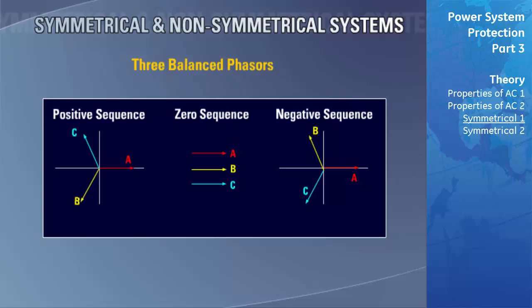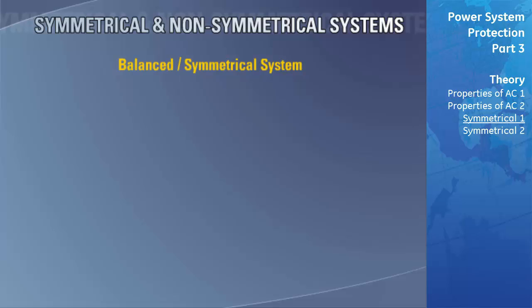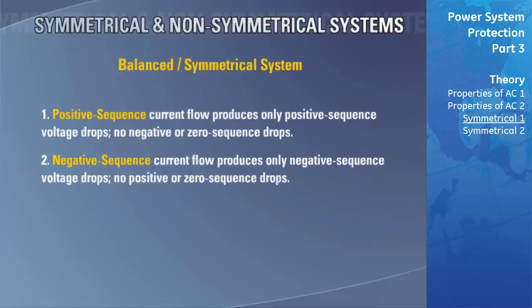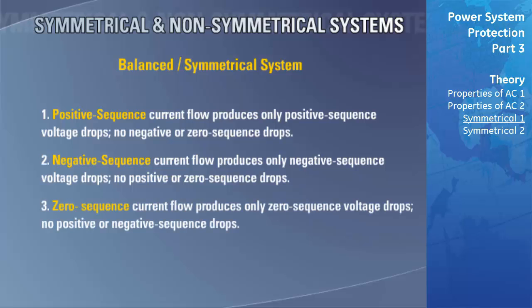Most microprocessor-based relays operate on symmetrical component quantities. According to Fortescue's methodology, a three-phase system has three sets of components — positive, negative, and zero — for both current and voltage, and they are independent of each other. Positive sequence has a phase rotation of ABC, consisting of equal-magnitude phasors displaced 120 degrees apart, rotating counterclockwise. Negative sequence has rotation ACB. Zero sequence phasors have the same magnitude and are in phase with each other with no rotation sequence. In a balanced system, positive sequence currents produce only positive sequence voltage drops, and likewise for negative and zero sequence.